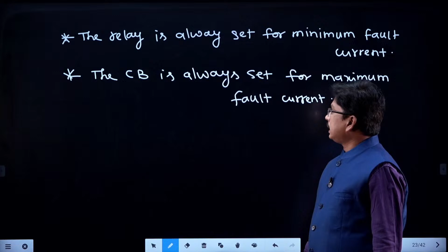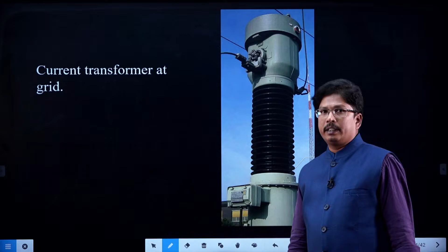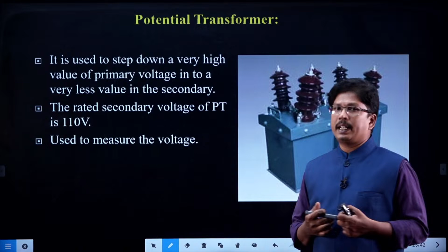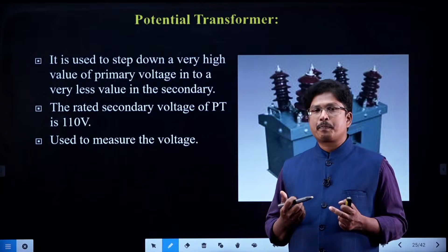Right students? Right. And the next element is the current transformer, this is the current transformer we have in the grid location. Next one is the potential transformer, same as the current transformer. The potential transformer is stepping down the voltage, so it is a step down transformer. The rated secondary voltage is generally 110 volts. We have measuring type PT and protecting type PT also. The protecting type of PT can be used as the over voltage relay, right?